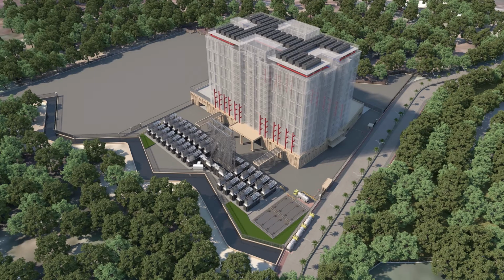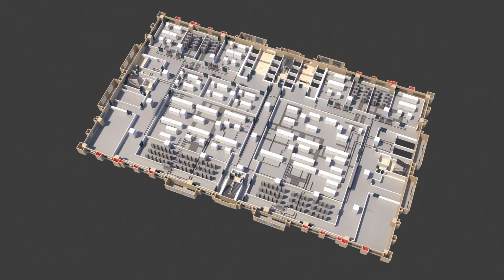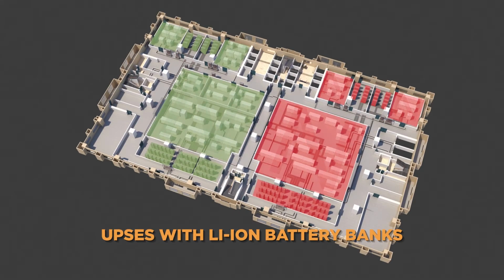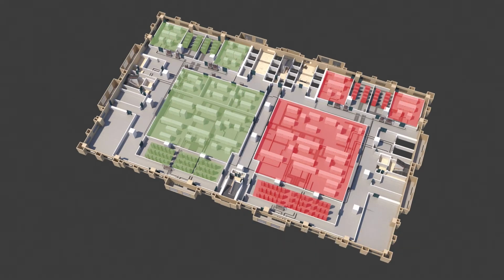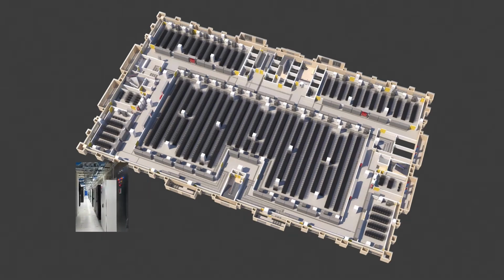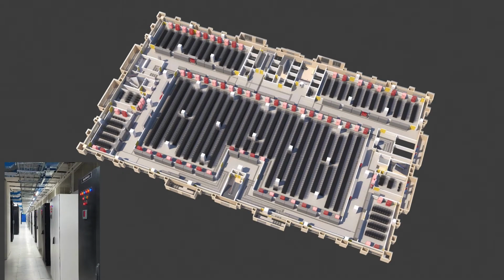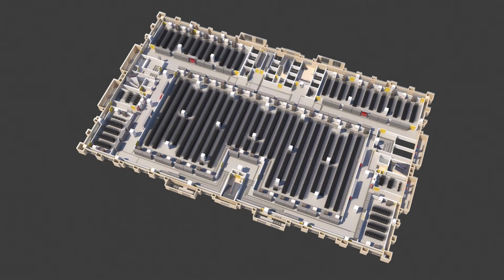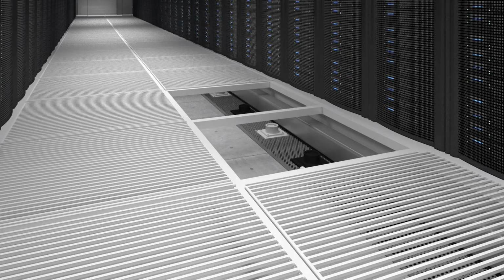The power is carried to the UPSs, stationed on the various UPS floors, through redundant riser ducts on two opposite sides of the building. For each server hall floor, there are 6.4 megawatt equivalent UPSs with N plus N redundancy, backed by lithium-ion battery banks with the two ends of the UPSs and batteries in separate rooms. These UPSs supply power to PDUs. Two separate PDUs getting power from two different UPSs supply N plus N power through industrial-type sockets and power cables to the racks.